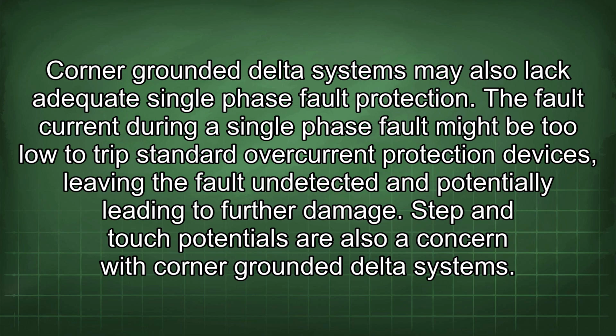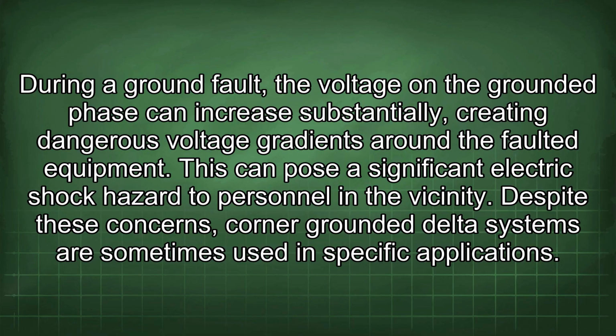Step and touch potentials are also a concern with corner-grounded delta systems. During a ground fault, the voltage on the grounded phase can increase substantially, creating dangerous voltage gradients around the faulted equipment. This can pose a significant electric shock hazard to personnel in the vicinity.